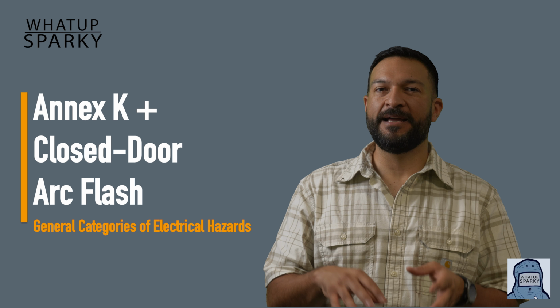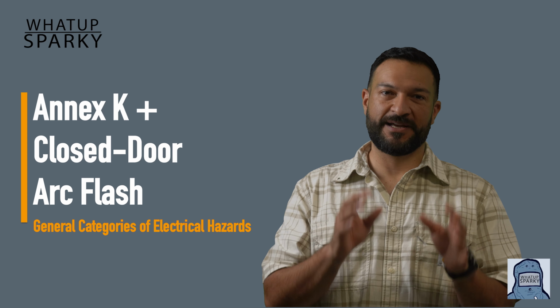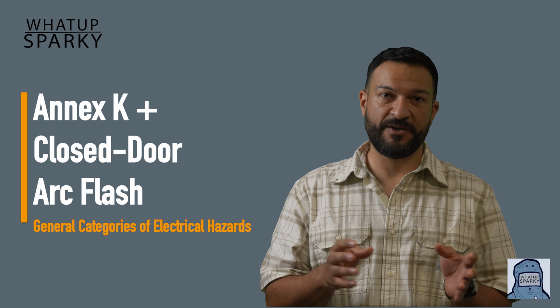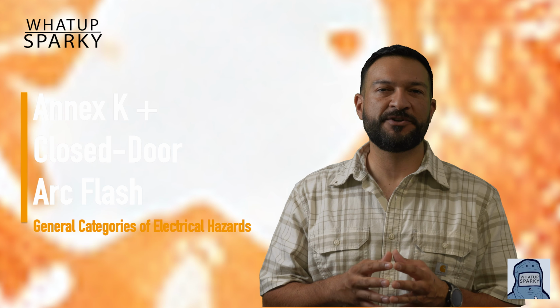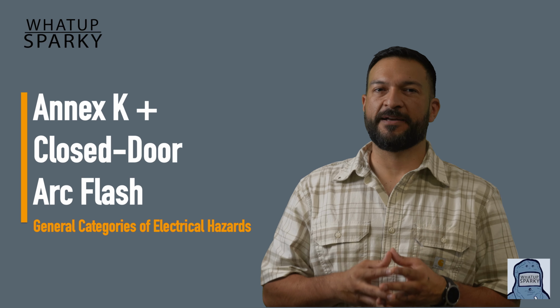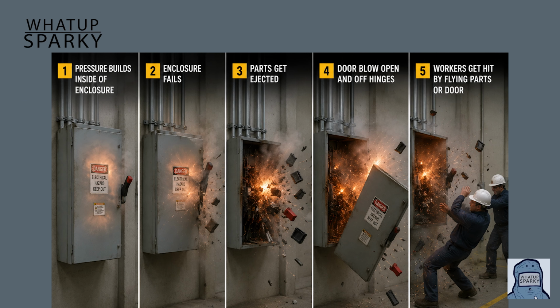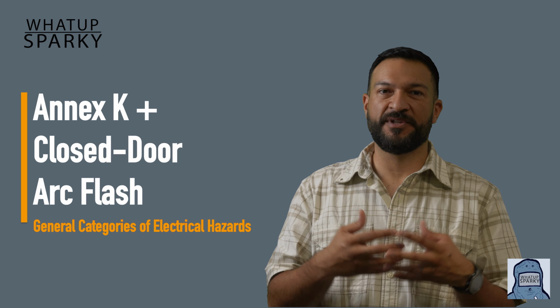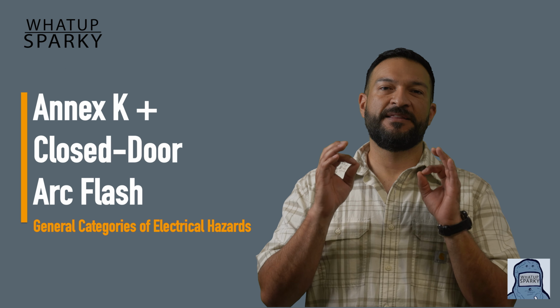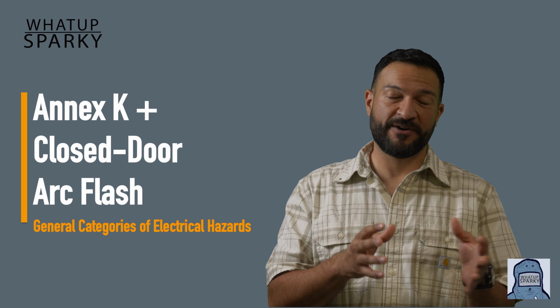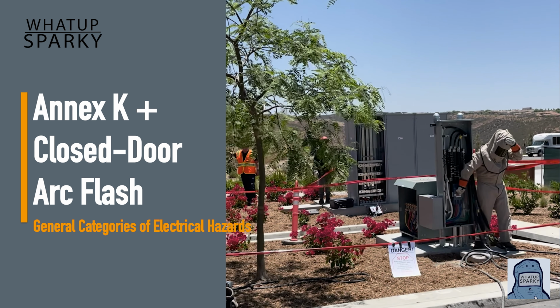So Annex K, general categories of electrical hazards, got a major rewrite. The old vaporized copper expansion theory of arc blast pressure, NFPA walked that back. The new explanation is that pressure builds inside of the enclosure, it fails, parts get ejected, and the doors blow off the hinges. Workers get hit by the flying parts or the enclosure components. That changes how you think about closing a breaker with the door open versus closed.